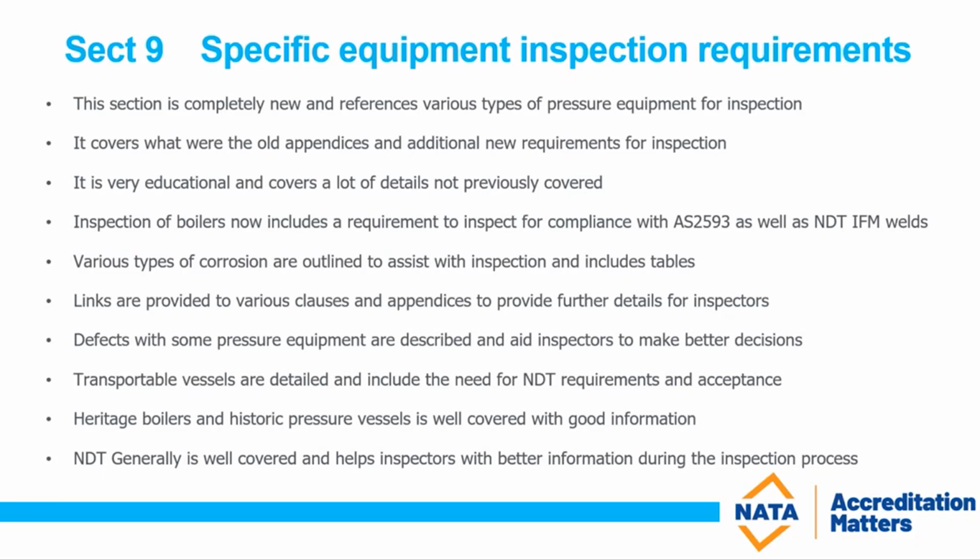And we also had a question submitted earlier last week about clause 9.2 from Frank Bush. So clause 9.2, where it talks about in addition to other additional inspection and checking at intervals not greater than 4 years for fire tube boilers. So it's this clause. And then his question is that the main issues raised with him by operators are the costs of lagging removal and replacement, NDT, loss of production, having to retest welds on a 250 psi boiler when operating at 150 psi.